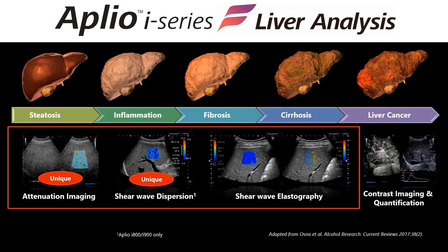Shear wave dispersion, Canon's unique enhancement of conventional shear wave, displays and quantifies the shear wave dispersion slope, which is related to liver viscosity. Recent studies suggest that the dispersion slope can help provide a quantitative non-invasive assessment of lobular inflammation in patients with NAFLD and NASH. Last but not least is our attenuation imaging, which is a reliable and accurate tool for the assessment of hepatic steatosis. It's well understood that a fatty liver is more attenuating, and now clinicians have an imaging method to detect and quantify attenuation in patients with steatosis.